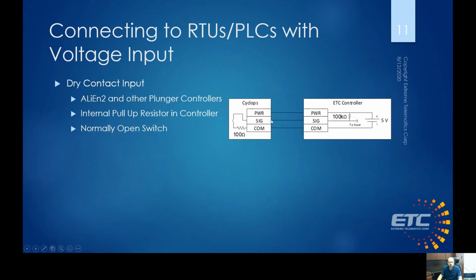And so when it's open, there's no circuit, you don't have a voltage coming back in SIG. So this pull-up to power allows the input on the microprocessor to see a positive voltage or a high voltage when there's no arrival. And then, as we mentioned before, when the arrival is signaled, we close this switch and signal is connected to common or ground, and that'll pull it low. So it'll go from being high on a non-arrival to low during an arrival.